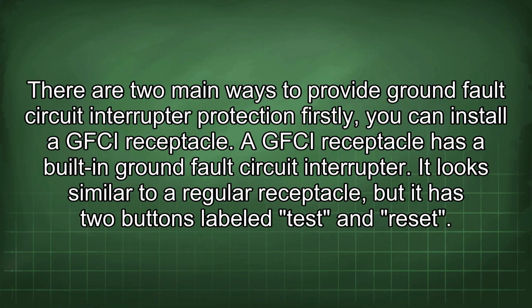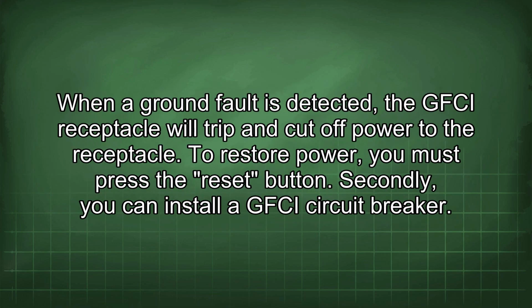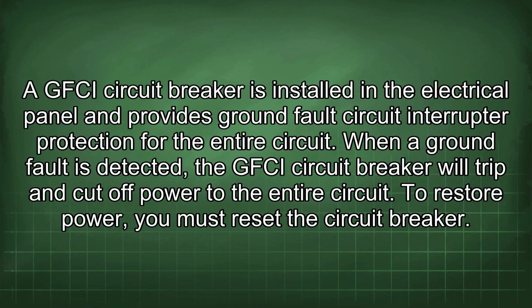There are two main ways to provide ground fault circuit interrupter protection. Firstly, you can install a GFCI receptacle. A GFCI receptacle has a built-in ground fault circuit interrupter. It looks similar to a regular receptacle, but it has two buttons labeled Test and Reset. When a ground fault is detected, the GFCI receptacle will trip and cut off power to the receptacle. To restore power, you must press the reset button. Secondly, you can install a GFCI circuit breaker. A GFCI circuit breaker is installed in the electrical panel and provides ground fault circuit interrupter protection for the entire circuit. When a ground fault is detected, the GFCI circuit breaker will trip and cut off power to the entire circuit. To restore power, you must reset the circuit breaker.